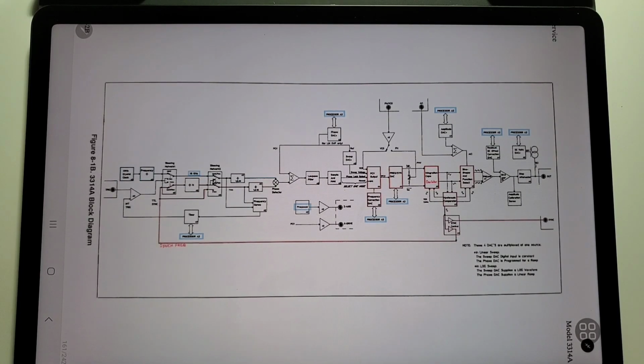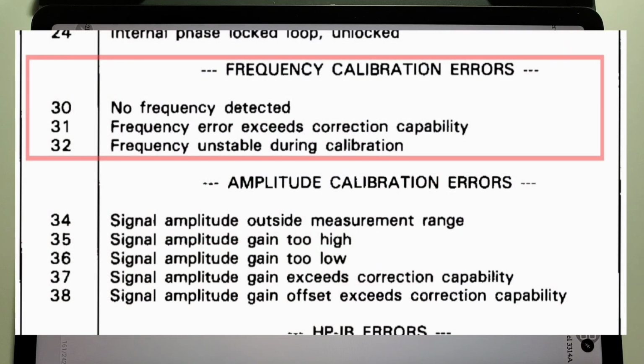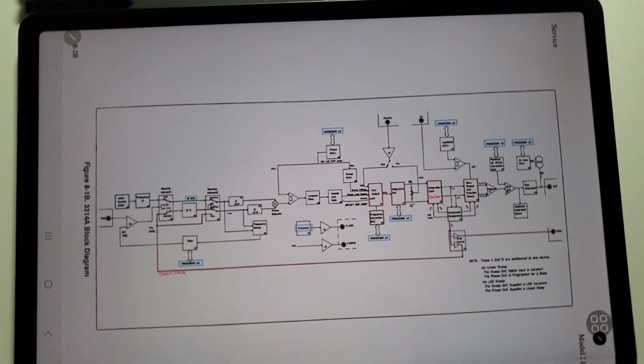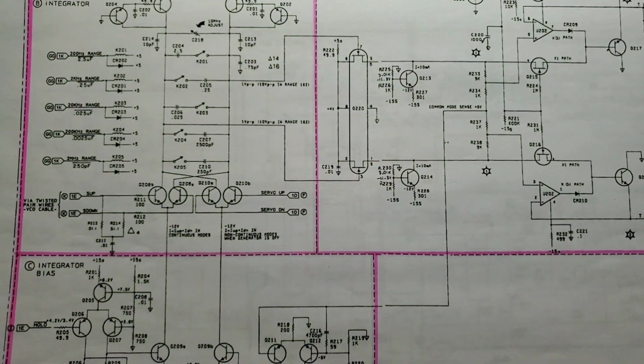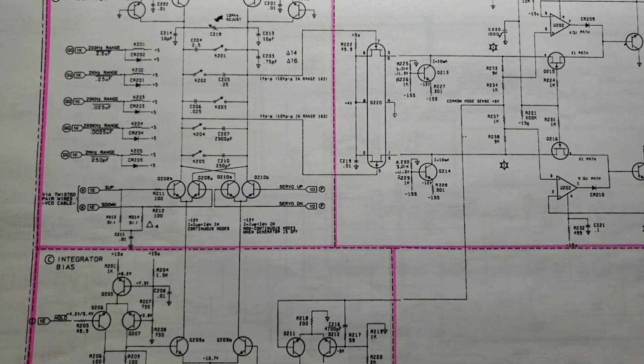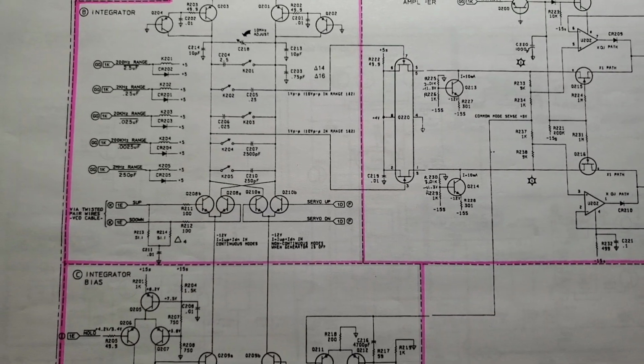And if for some reason it is not able to, then the CPU may, after 5 tries, display a calibration error, indicating that it cannot steer the frequency to correct it, or that even after applying all the corrections, it's still off by a certain percentage, or that it cannot sense any frequency at all. By the way, for amplitude calibration, there are similar processes and errors, so let's hope we don't see any of that. Of course, the actual circuits are complicated, and I will research and learn more details over time, but grasping the high-level operation has been helpful to make it easier to understand the circuit diagrams.